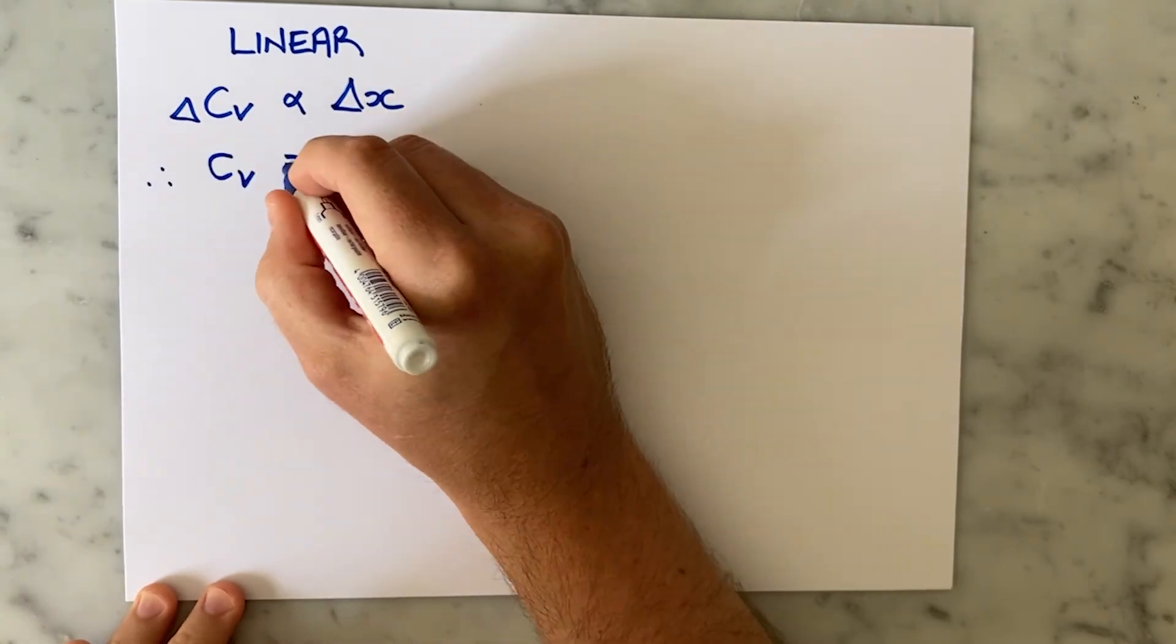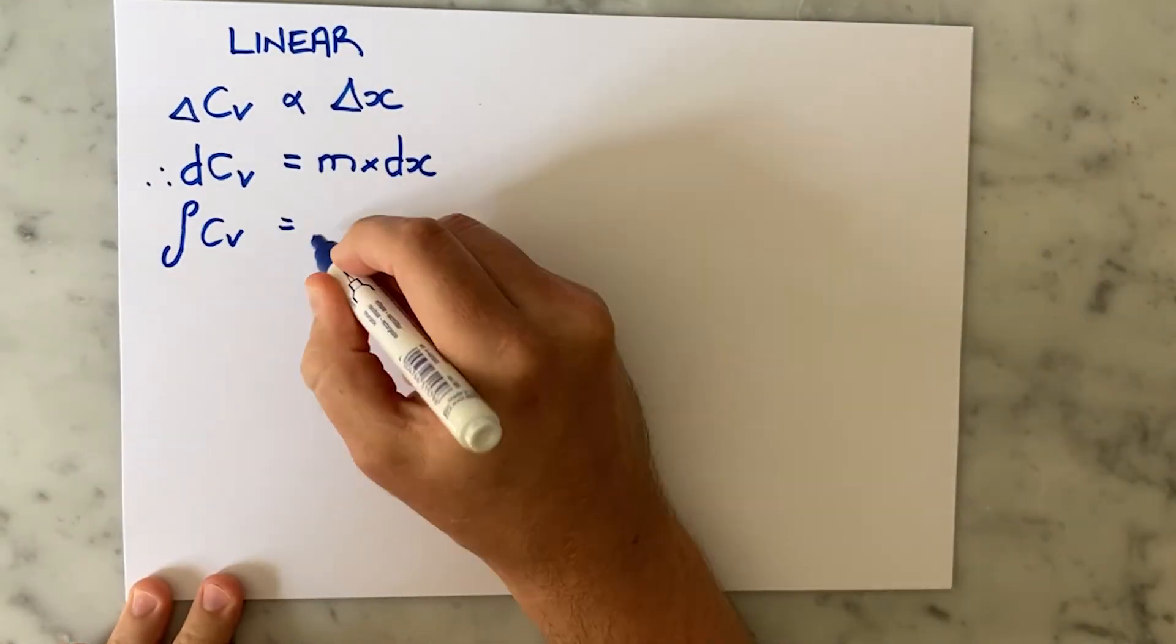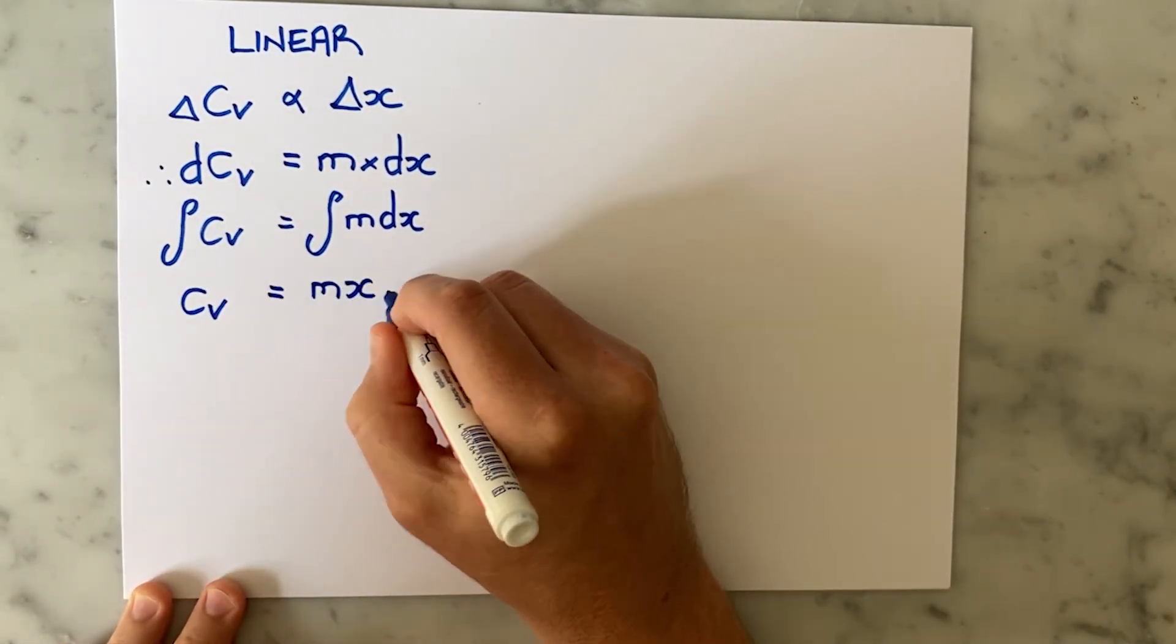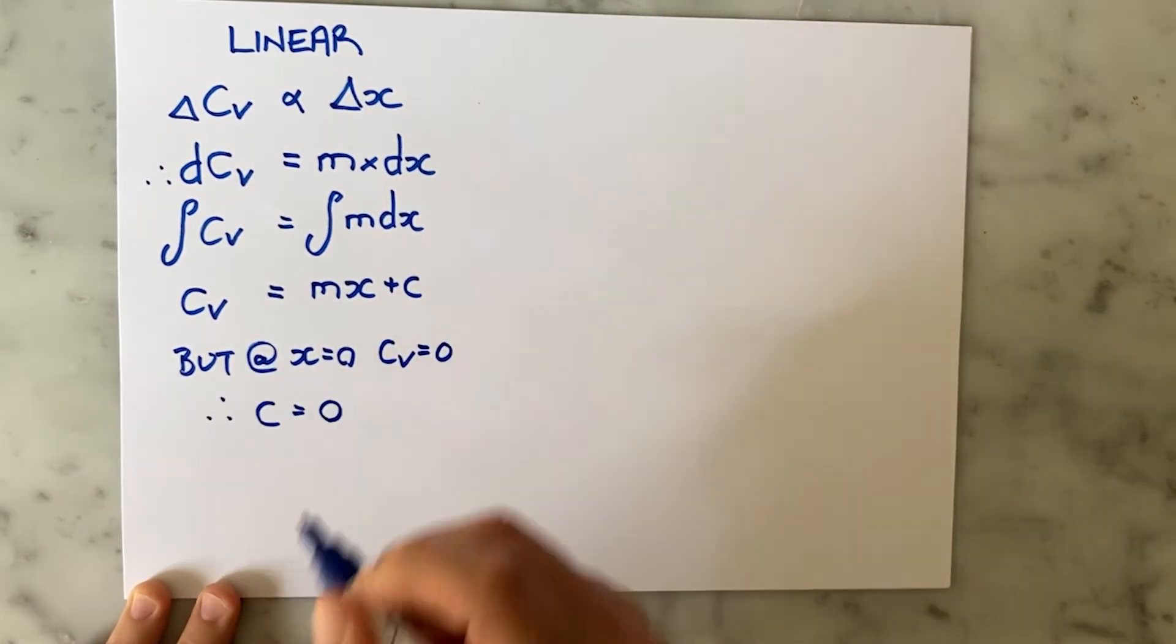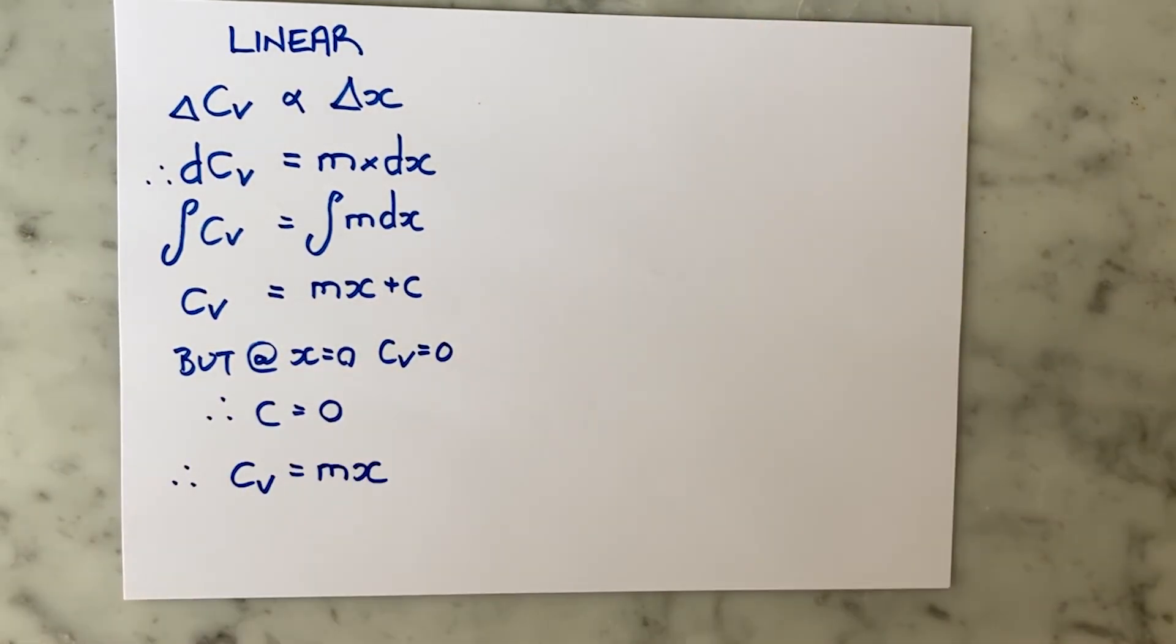For a linear valve, the change in CV is proportional to the change in valve opening. So we call the proportionality constant M and the constant of integration C simply equals 0 because we know that when the valve opening is 0 so is the CV, just like we said earlier.